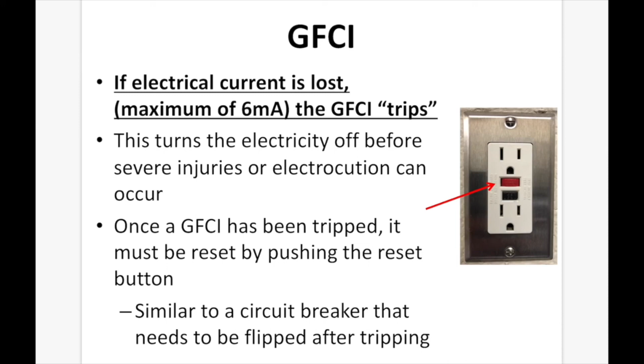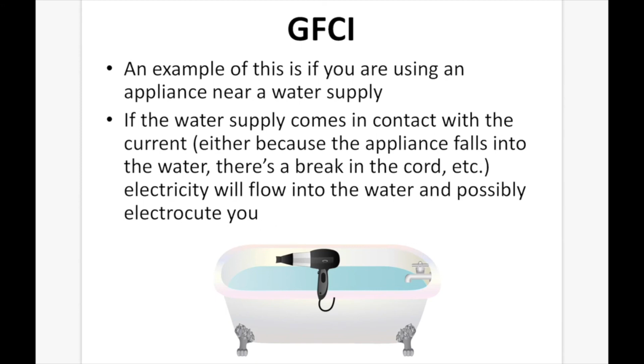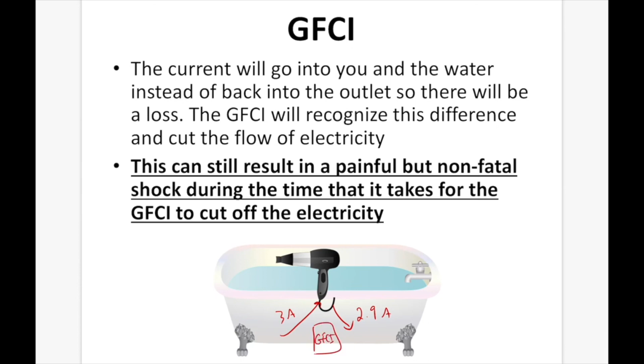An example of using the GFCI is if you're using an appliance near a water source. If the water supply comes in contact with the current, either because the appliance falls into the water, there's a break in the cord, etc., electricity will flow into the water and possibly electrocute you. The current will go into you and the water instead of going back into the outlet, so there'll be a loss. The GFCI will recognize this difference and will cut the flow of electricity immediately. This can still result in a painful but non-fatal shock during the time it takes for the GFCI to cut the electricity. So if you have, let's say, 3 amps coming in and only 2.9 amps going back towards the outlet, the GFCI outlet is going to recognize that the current out was not equal to the current in. The GFCI is going to shut down the current before it can cause electrocution.